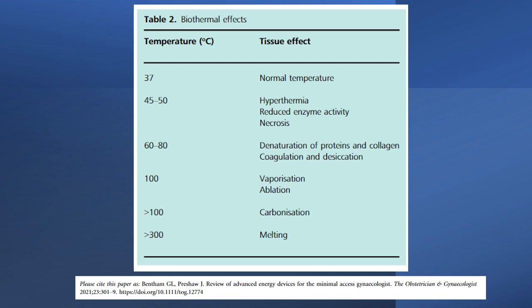Biothermal effects. This table is talking about the temperature and the effect on the tissue. So 37 degrees Celsius, the tissue effect is normal temperature. 45 to 50 degrees Celsius, tissue effect is hyperthermia along with reduced enzyme activity and necrosis. 60 to 80 degrees Celsius, denaturation of proteins and collagen coagulation and desiccation. 100 degrees vaporization and ablation, more than 100 degrees carbonization, more than 300 degrees Celsius melting.